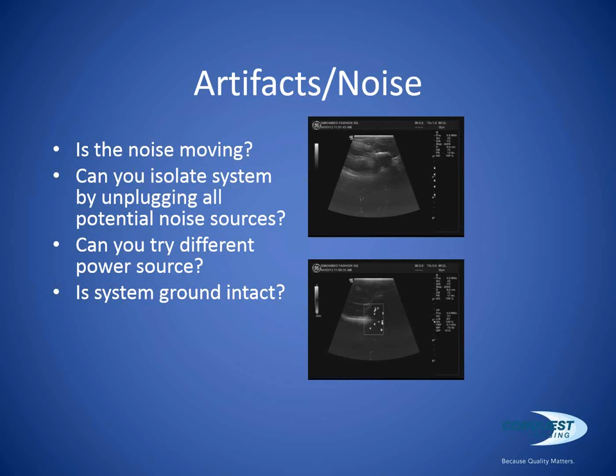But if you look at this image, this is a GE LOGIQ 9, and you can see it's kind of hard to tell, but there is some 2D and color noise, you can see the color noise speckle in the lower image. This has to do with the card cage cover ground not being intact. On the GE LOGIQ 9, this is a fairly common problem where the area between the card cage cover and the card cage becomes oxidized, and the solution is to clean all contact areas and the noise will go away. But we want to start examining system grounds, is the system grounded properly?